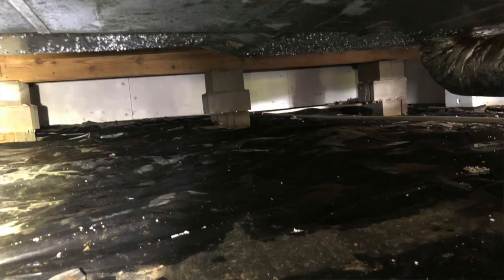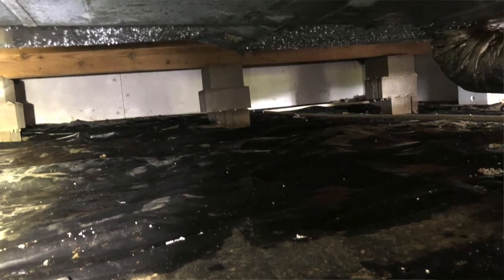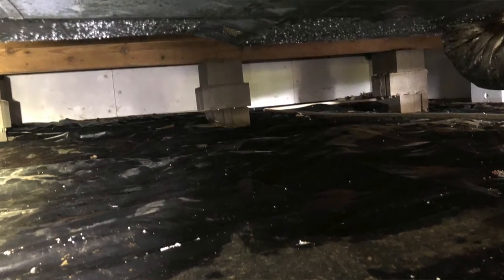With those complex layouts, there's just no way to get good airflow with foundation vents — it just doesn't make sense. Another issue is in the summertime, if you have your HVAC system ducted through the crawl space: you've got the AC blowing nice and cold, and with all those vents open you're letting that hot, humid air into your crawl space. That air hits the duct work and it's just going to condensate and sweat like crazy, causing moisture issues.